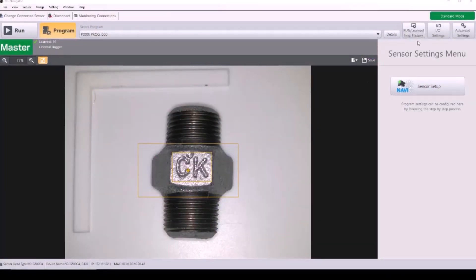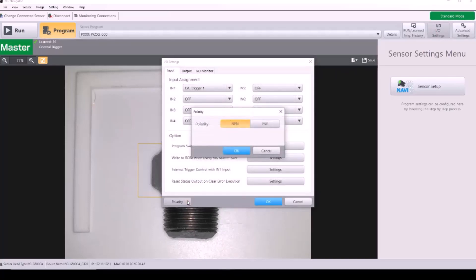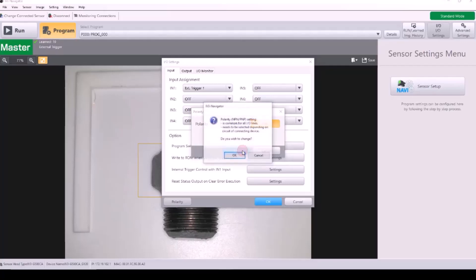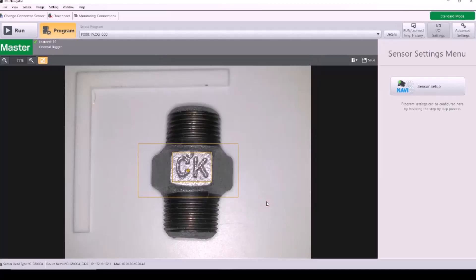Now I'm going to show you the settings that need to be changed or checked in the IV-3 software. Start by going into I-O settings, clicking polarity in the bottom left, and you can easily select back and forth between NPN or PNP. I'm selecting PNP for the setup to match my wiring configuration.